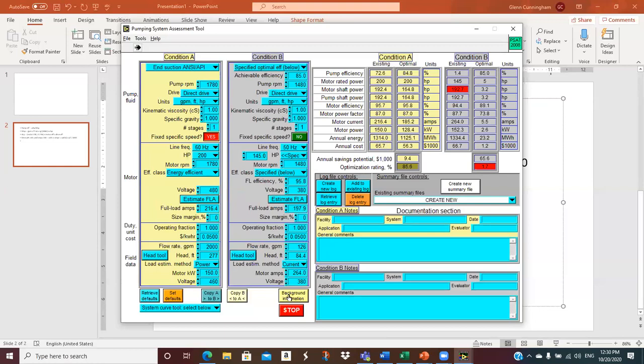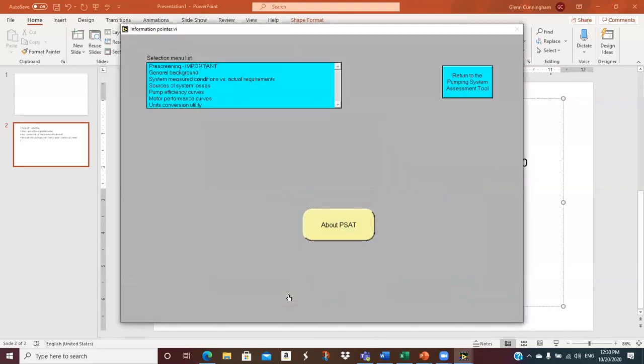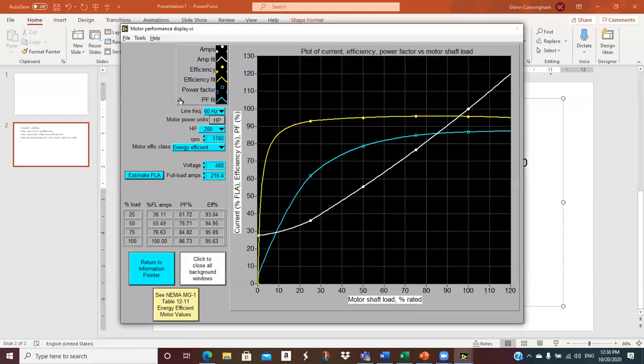Okay, now let me show you the background information. If you click this little box down here, background information, you got some pretty cool stuff. This is my favorite, motor performance curves. So looky here. Here you get information on power factor. We get percent full load amps, and we get motor efficiency as a function of the load on the motor. So down here, we've got shaft load as a percent of rated.